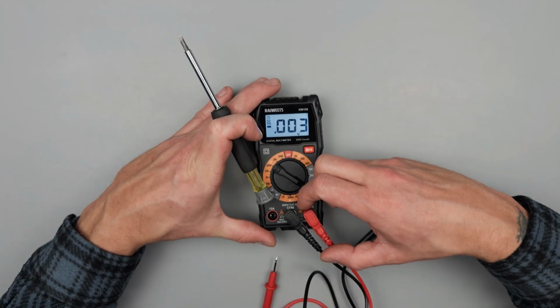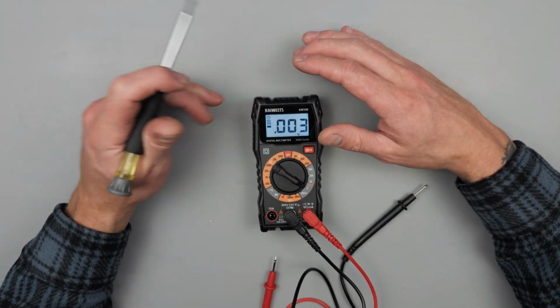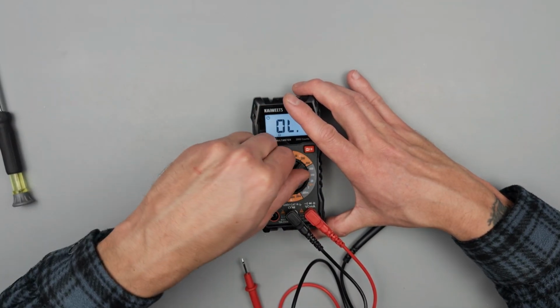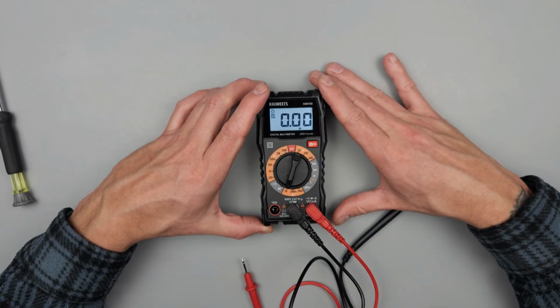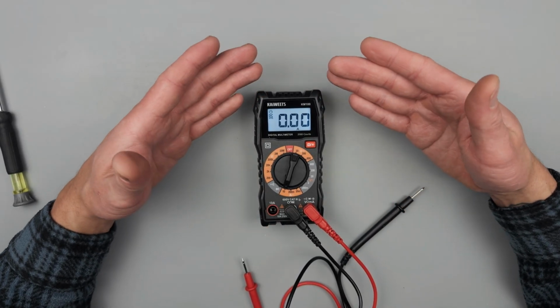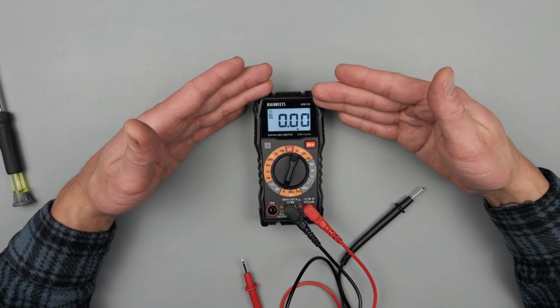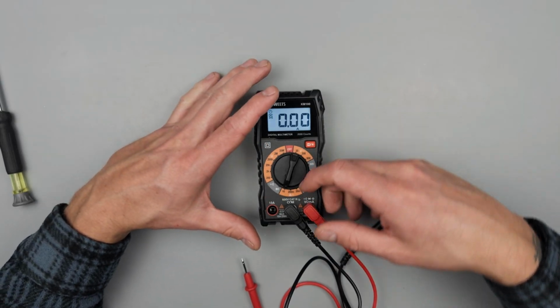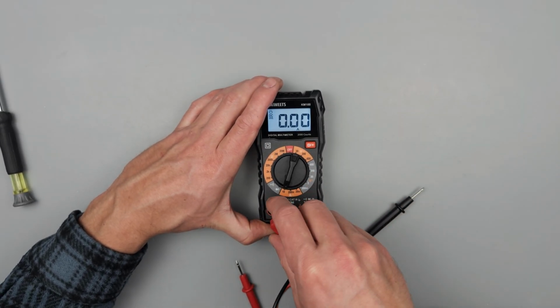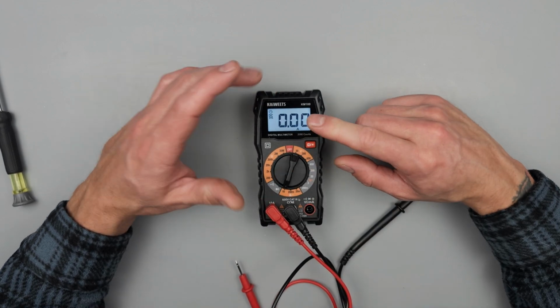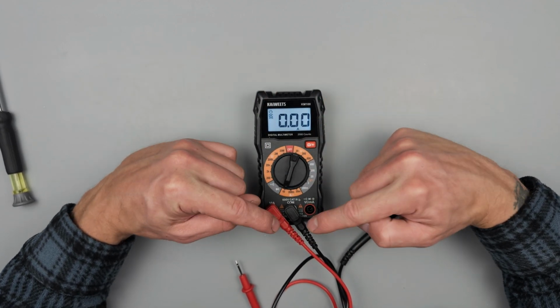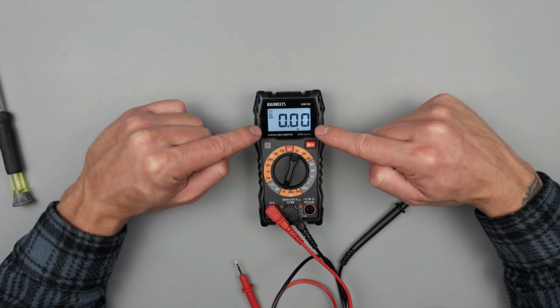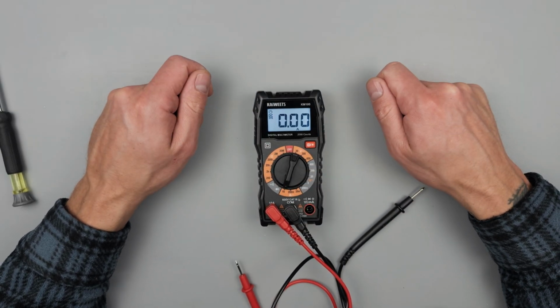The first thing that I'm going to do, if I'm going to make a current measurement, I'm going to put it to the biggest setting because I don't know how much current a circuit's going to produce, right? That's why I'm using the multimeter in the first place. I'm going to set it to 10 amps current, and I'm going to move my red lead over to here. I want to be very mindful that now in this configuration, my meter is a jumper wire.